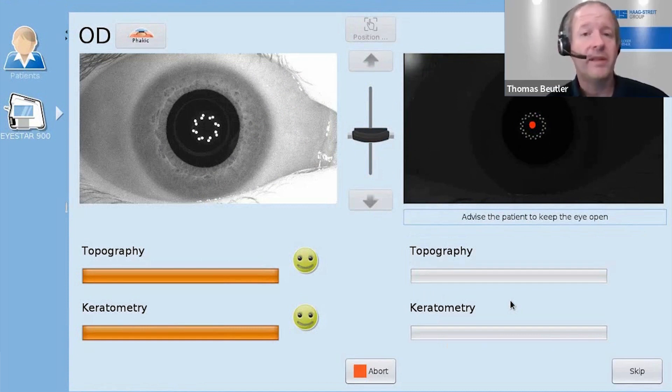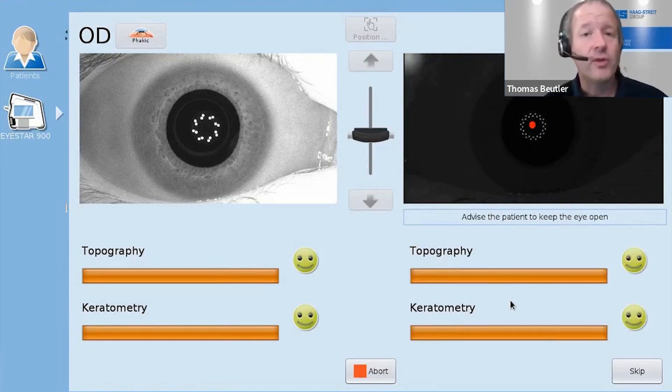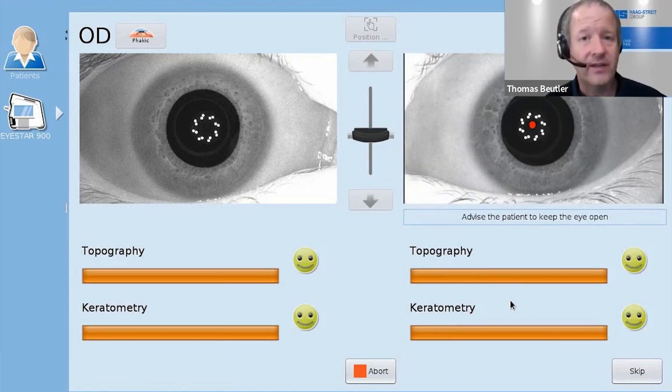It is a fully automated data acquisition which we have with the Eyestar. A bilateral measurement usually just takes about 40 seconds. If it's not fully automated you would have to do a lot of things, and if you have to do a lot of things you can make a lot of mistakes.